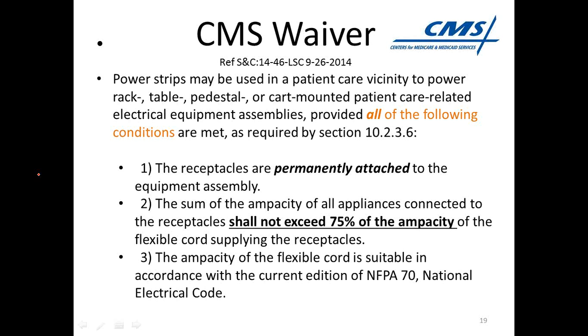I've actually extended this to say if it has a circuit breaker, don't let it exceed 75% of the ampacity of the circuit breaker, because in almost all cases the circuit breaker is rated at a lower amperage than the power cord is itself. So I go with 75. If it's got a 15 amp breaker, you take 3/4 of that, so you say about 12 amps is all the current that should be drawn through this unit.